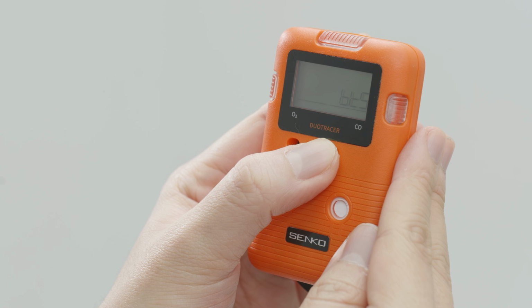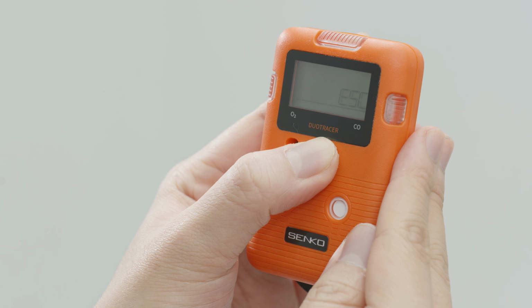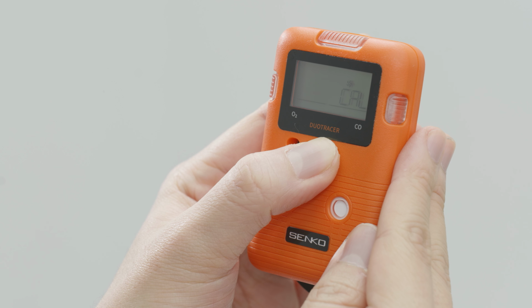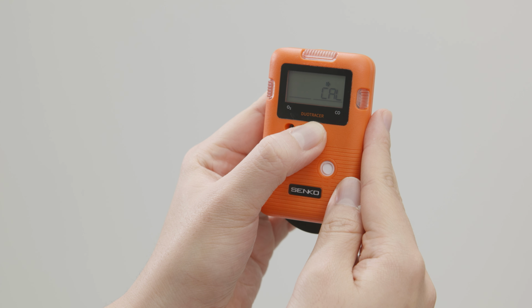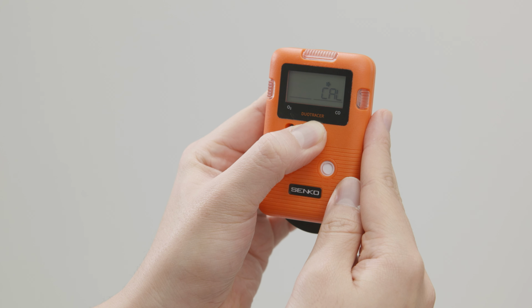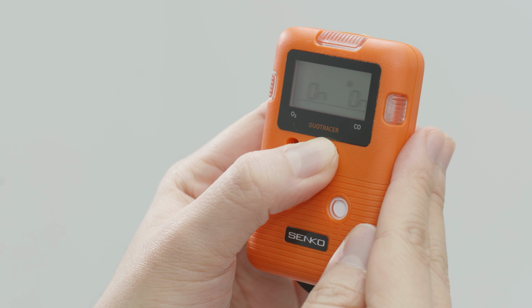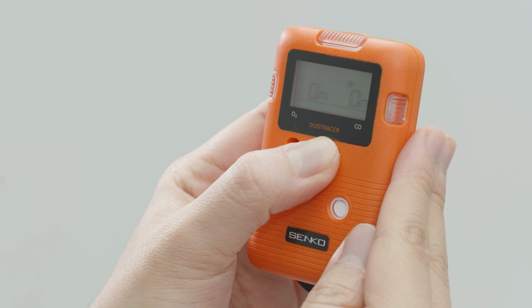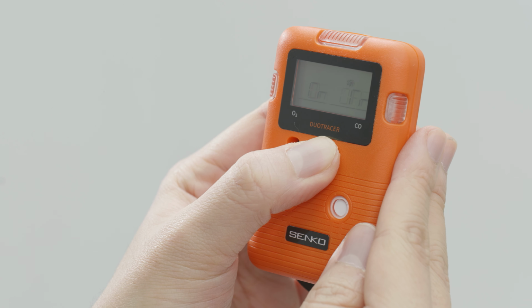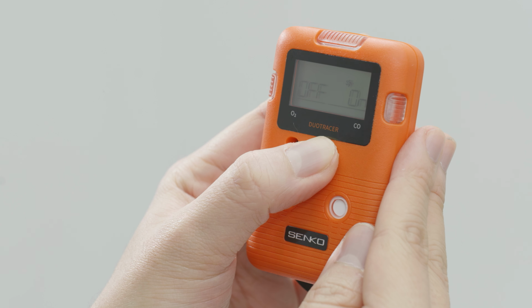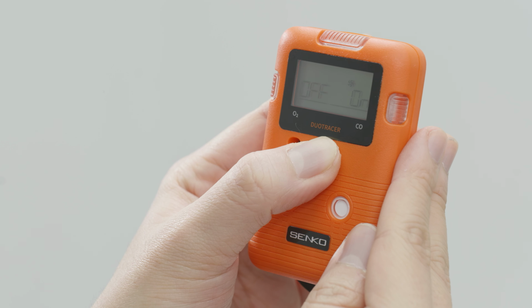If you want to perform zero calibration, look for the air icon on the screen, then press and hold the button to start zero calibration. Now, one important thing to remember, since Duo Tracer measures two gases at the same time, you'll need to select the gas channel you want to calibrate before starting the calibration process. Here's what the options on the screen mean. On means you'll calibrate both channels. On-off means only channel A will be calibrated. Off-on means only channel B will be calibrated.